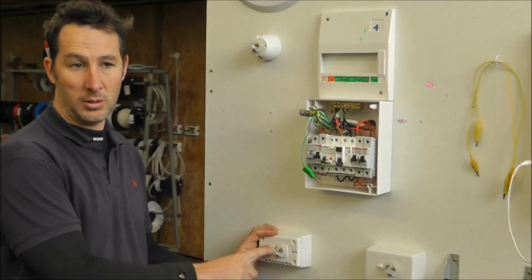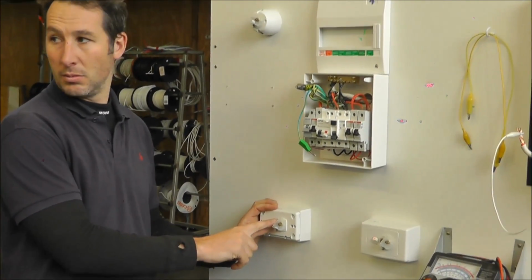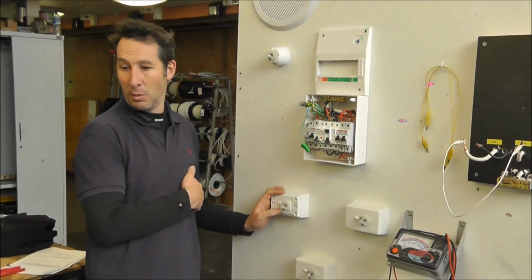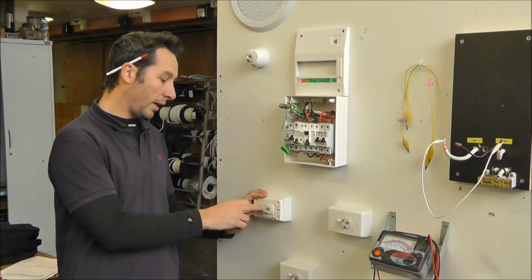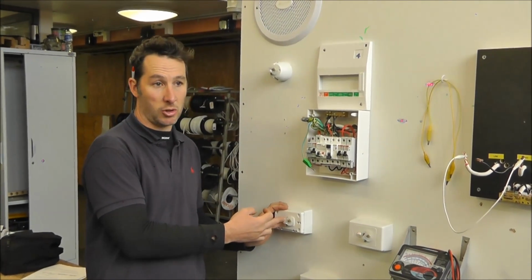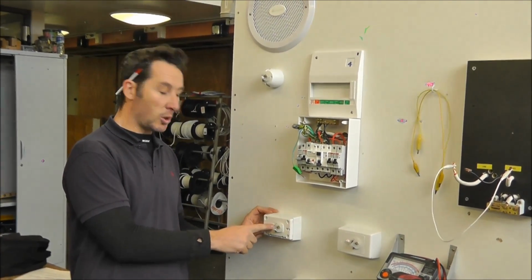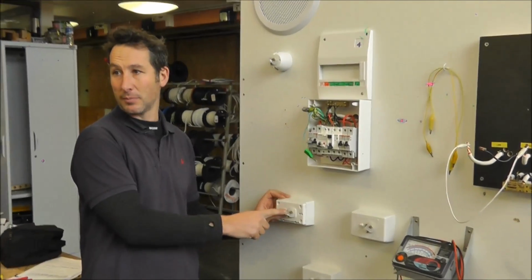That's a switching terminal. Someone's mucked it up. Someone's not been concentrating, for whatever reason, when they fitted it off and put active and neutral. So that's the only switch terminal in the socket outlet. We happy to say that?